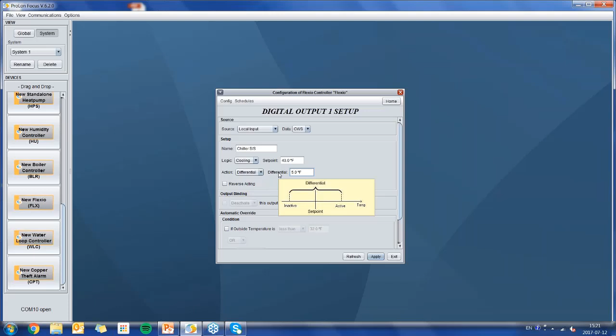We also have override conditions. For example, if the outside temperature gets below, let's say, 25 degrees, you can choose what the output should do. Do we want to keep it on or off? I could say if it ever gets colder than 25 degrees outside, I want my chiller to stay off, since I probably don't need it anyway.